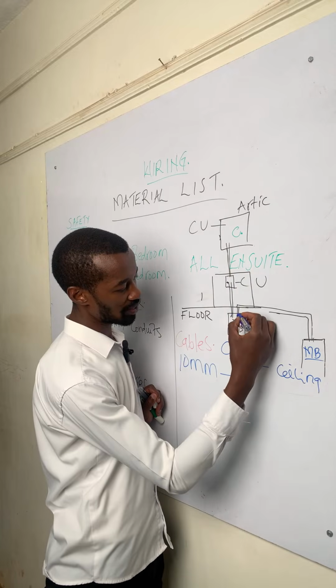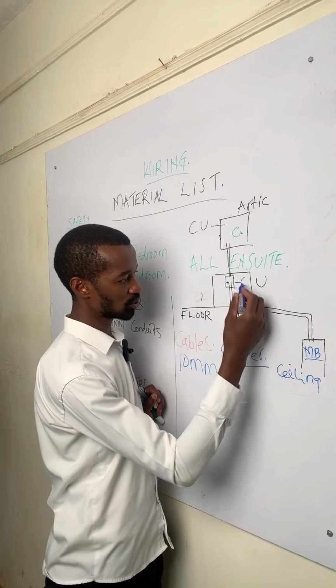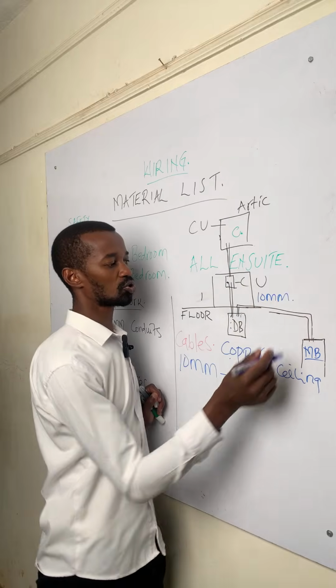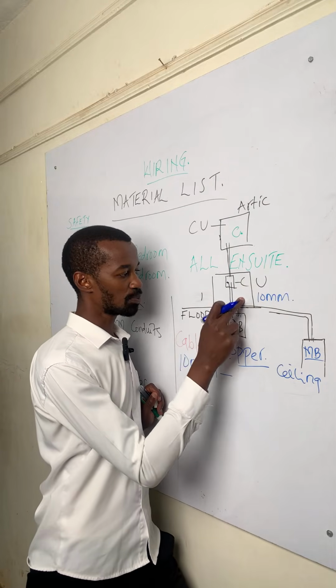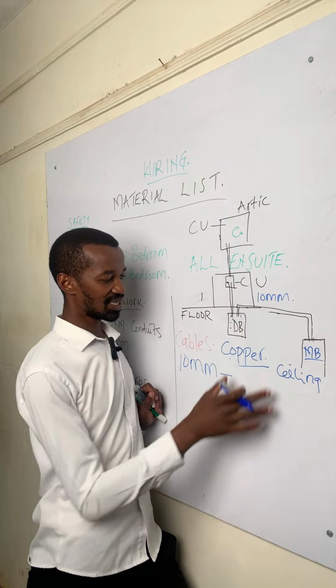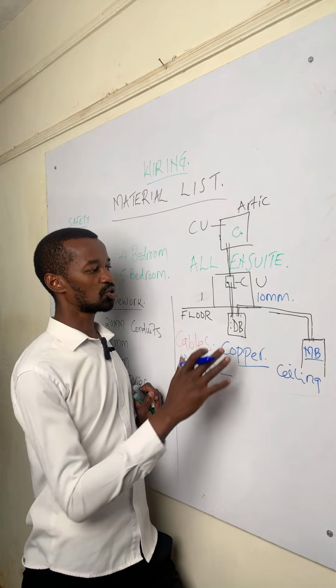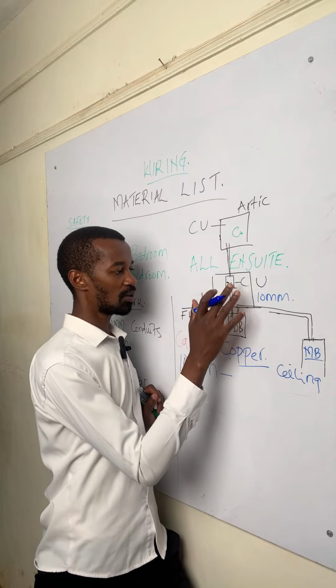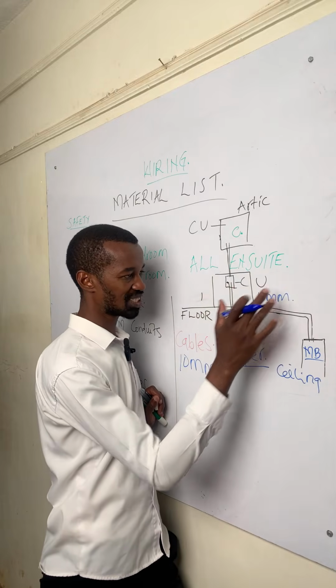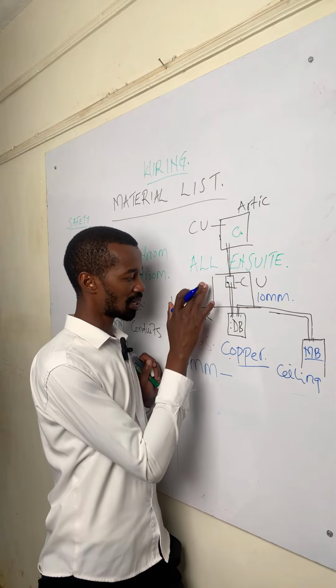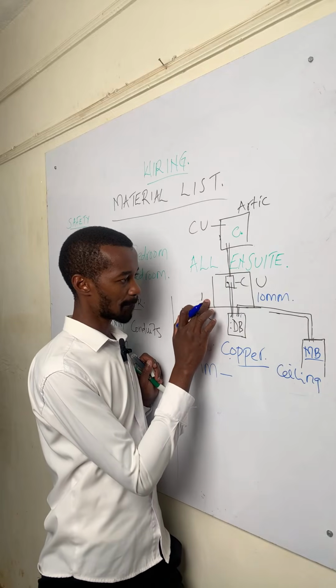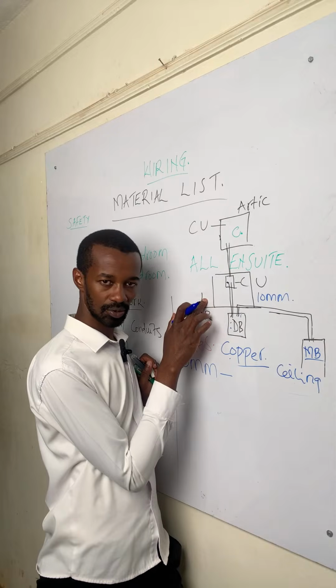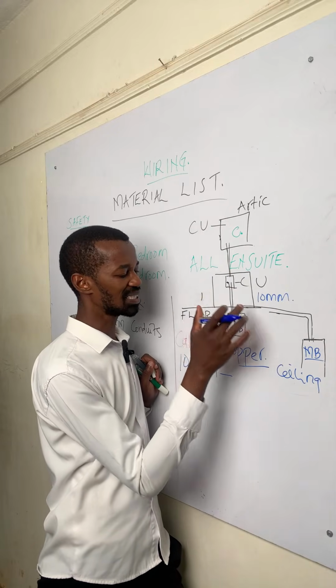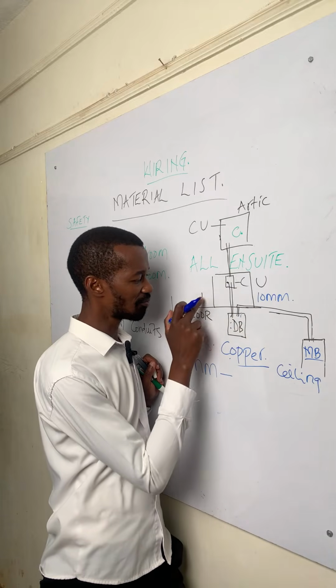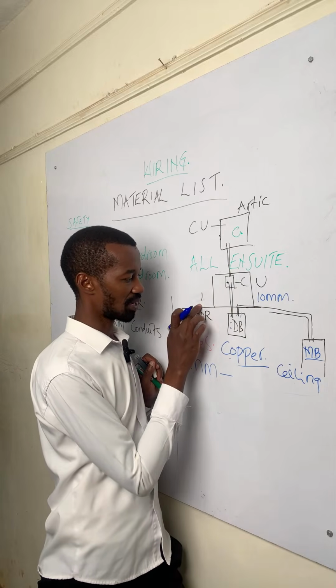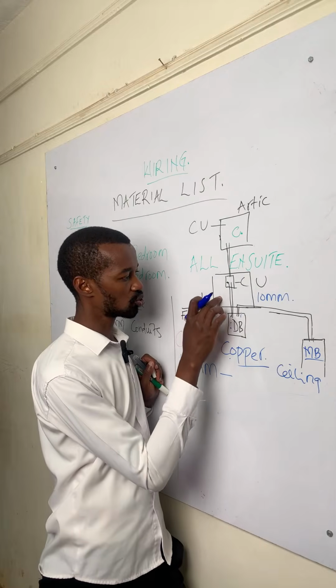I'll also add that from the first distribution board to the second consumer unit, let's also use a 10mm cable, because you can't dictate what people will connect or plug in within that common area. The kitchen may be located on one side, but what if they decide to modify their home and have a makeshift kitchen elsewhere? I've worked with clients who wanted a big space left for that, so someone upstairs doesn't have to go all the way down to the main kitchen - there's a name for that I'm forgetting - so they can simply fix something there, like a cooker, so ensure there's a provision for that.